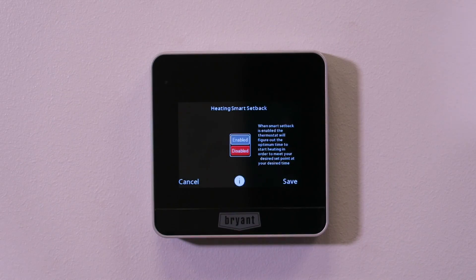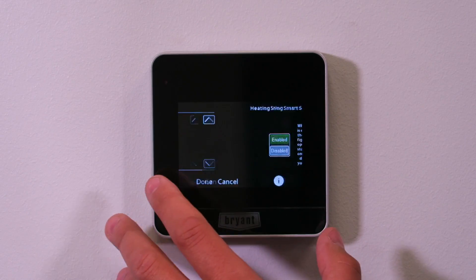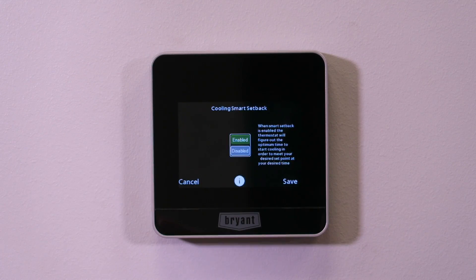The longer your setback range is, the more advantageous this feature will be. If you're only in away mode for an hour, it's not a big deal, but the more hours away from your house, the more it will play with your set points and save energy. If your customer finds it annoying, this is where you can disable it — but I would leave it on. It's extremely useful on heat pumps, because the compressor operating mode is probably 200 to 400 percent efficient depending on outdoor air temperature, versus backup electric heat which is only 100 percent efficient. Cooling smart setback works the exact same way but in cooling mode.